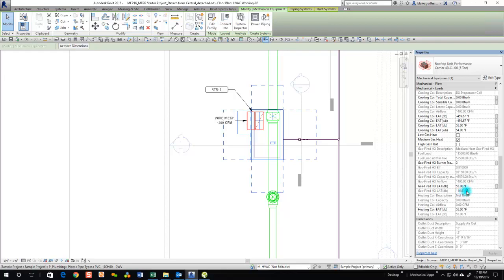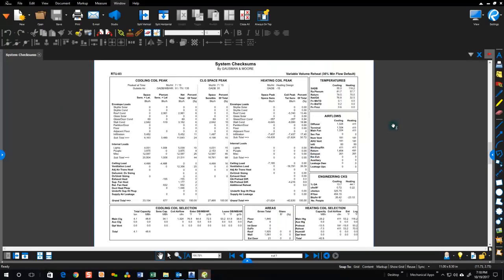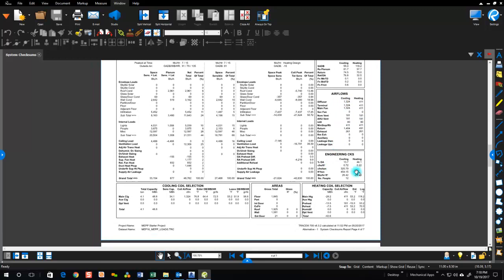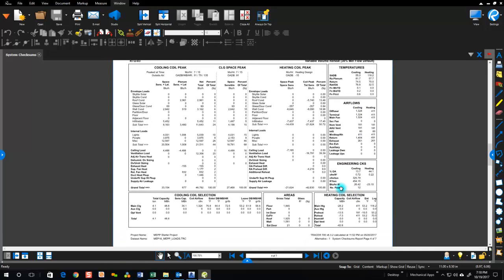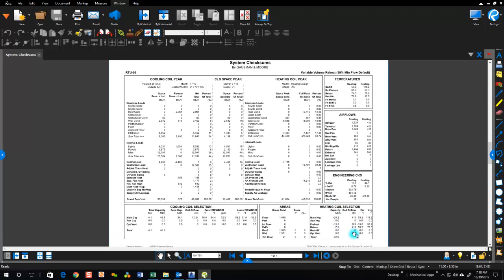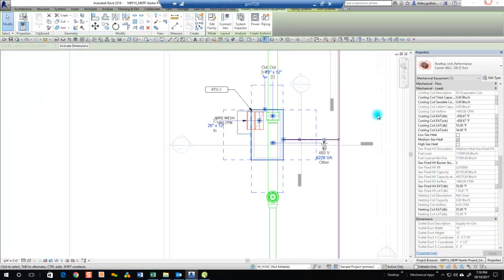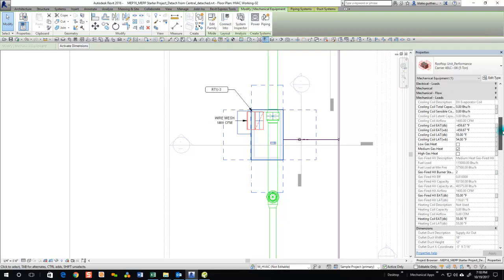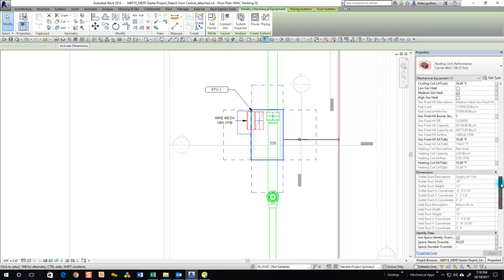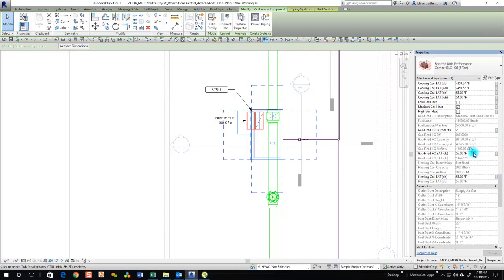So right now we're at 116 degrees Fahrenheit. If this 55 degrees entering is accurate, which it's not. So this is based upon 1324, but right now our mixed air temp is 53.2. So I guess it's pretty close. All right. So we could rebalance the diffusers to get down to the exact load. I'm going to keep it how it is right now. So with a 55 degree entering air temperature, the medium heat setting on this given unit is 116 degrees. Let's see what the low heat option looks like. 93 degrees. I like that one better.